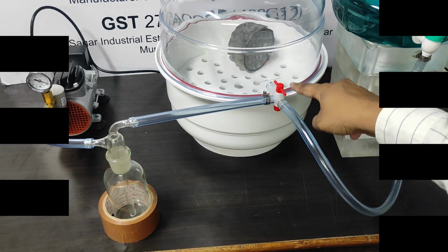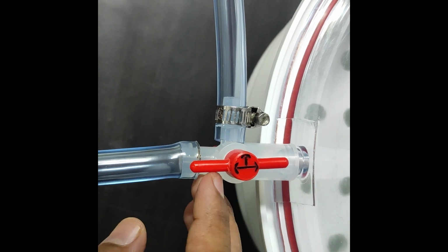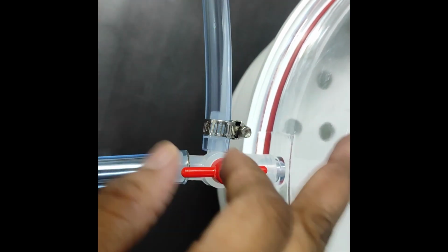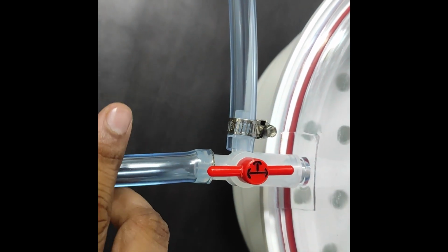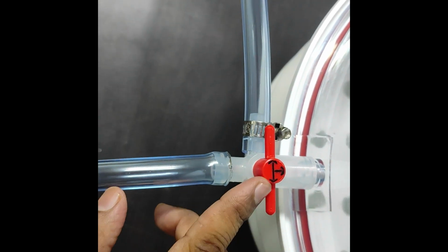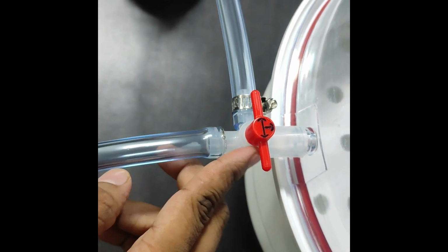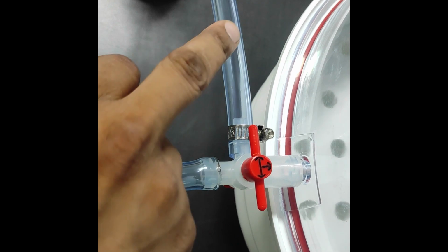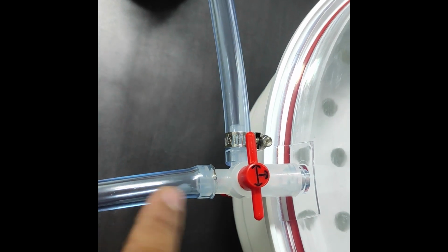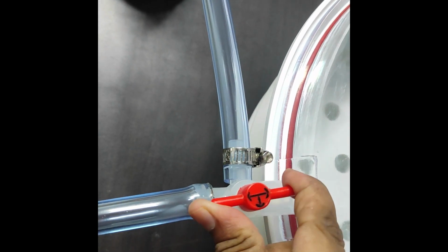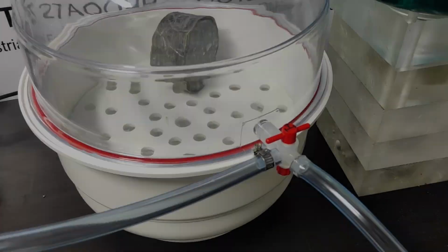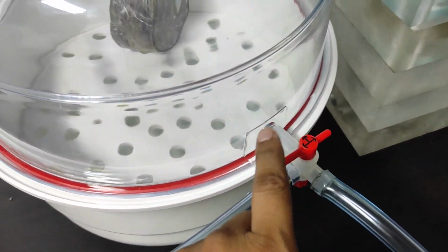So we will see actually how it works. Here we can see this kind of marking is done. When the valve is like this, this connection is on and this is also connected. All three are connected. If I want to isolate this one, I will have to keep it like this. So now this and this are connected. This is not connected because here there is no connection. So this connection and this connection are only on. If I want to isolate this one and turn on this and this, I will rotate it like this. So here this connection and this connection are on and this is isolated. So in the first step, we isolated the water pipe and we keep the arrangement like this.